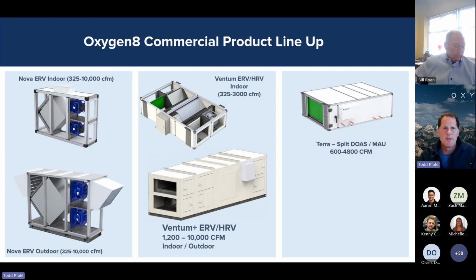All of our units share some commonalities. They all have double wall foam injected panels, so there's no insulation in the airstream. We have MERV 13 filters on the outside air, which is the recommended filtration requirement. We use ECM fans as standard, so reduced moving parts, very low noise and vibration, very energy efficient, can do variable air volume or constant air volume as standard, and easy to commission as well to adjust for any ductwork changes from your schedule. And everything comes with standard Distech DDC controls to make for a package plug and play solution.